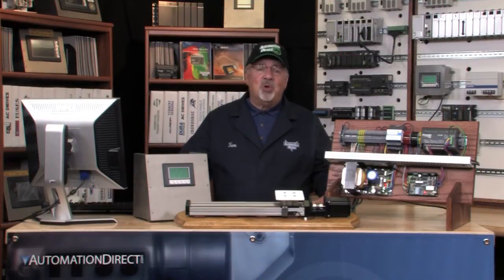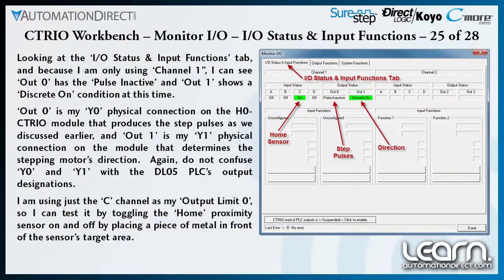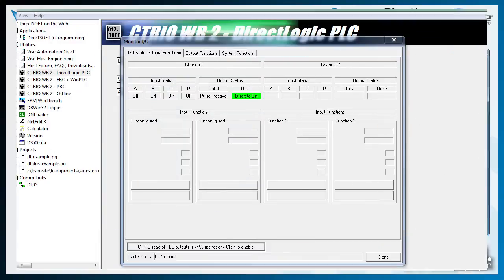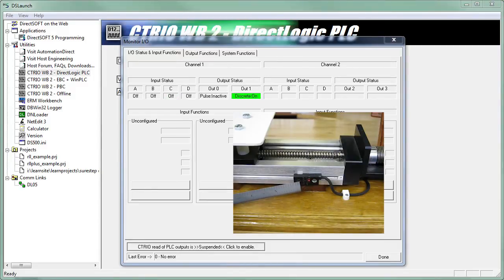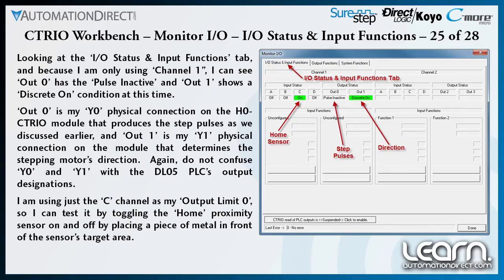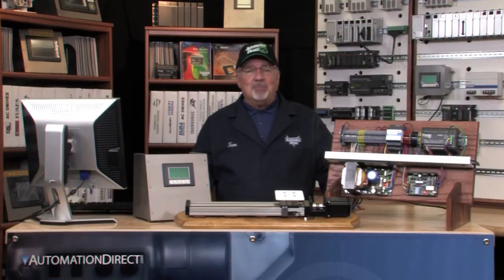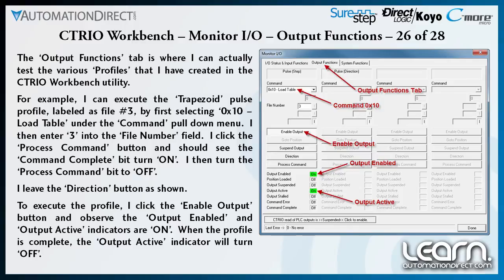I can monitor the CTRIO's inputs and outputs by looking at the I/O status Input Functions tab. I am using channel 1, so OUT0 shows as pulse inactive, while OUT1 shows a discrete on condition at this time. OUT0 is my Y0 physical connection on the H0-CTRIO module that produces the step pulses, and OUT1 is my Y1 physical connection that determines the stepper motor's direction. Please do not confuse Y0 and Y1 here with the DL05 PLC's output designations of the same name. I can test the C channel as my output limit 0 by toggling the home proximity sensor on and off by placing a piece of metal in front of the sensor's target area. From the Output Functions tab, I can test the various move profiles I have created.